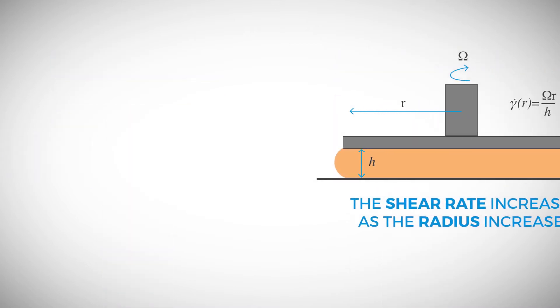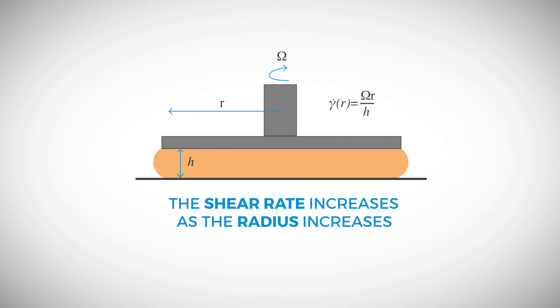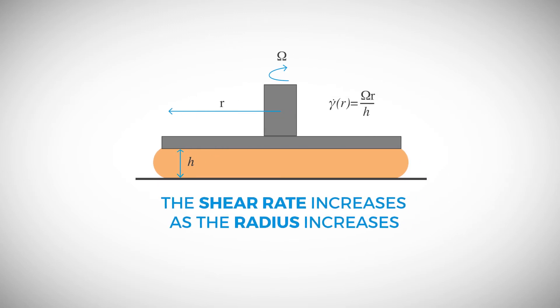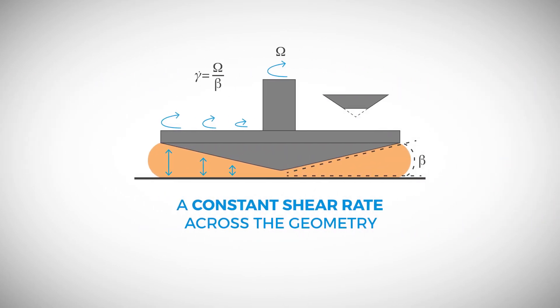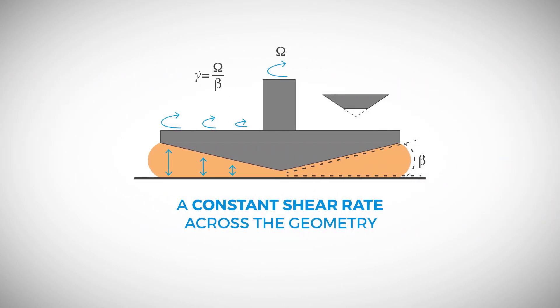One difference is the shear rate in the radial direction. For parallel plates, the shear rate increases as the radius increases. For cones, the change in slope results in a constant shear rate across the geometry. The constant shear rate makes the cone and plate useful for measuring normal stresses.